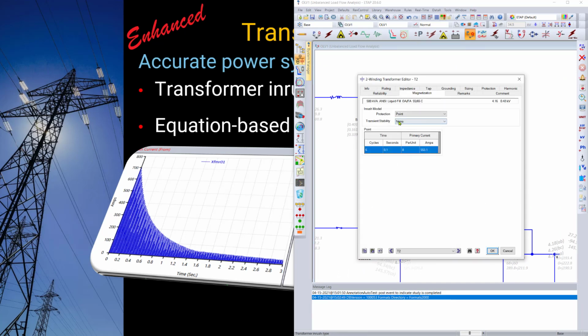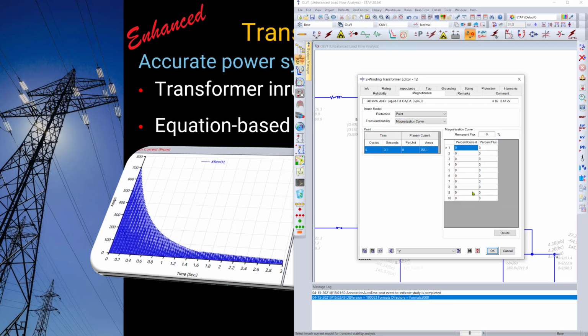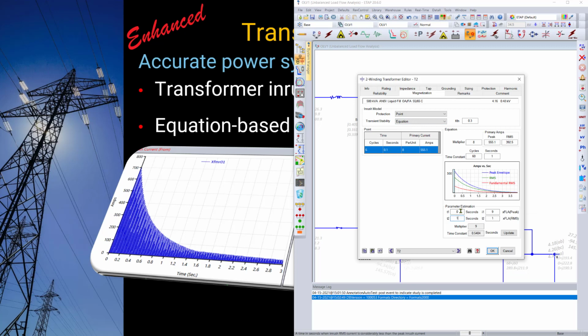Simply go to the magnetization page, and for transient stability you can use either a magnetization curve, which is point-based, that has current versus flux along with the remnant flux, or you can use an equation-based approach. The parameter estimation allows you to simply put in a time when the inrush current is at or close to its peak value, assuming that the transformer is energized at 0 seconds. If the assumption is that the peak happens at 0.1 seconds after energization, and the peak current at that time is the largest measured value, which is 10 times FLA, then you can simply allow the program to recompute the inrush multiplier and the time constant and update it directly into the chart.